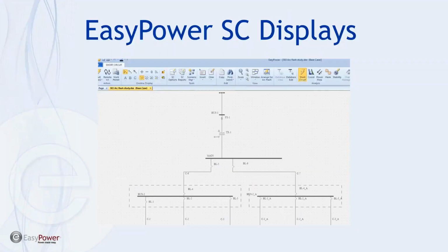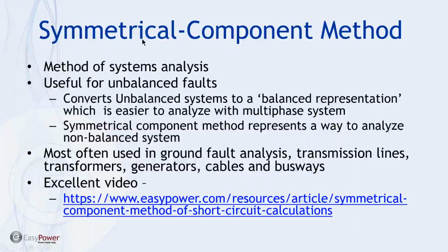Now, the next type of application of these terms is what's referred to as the symmetrical component method, and this is a method of systems analysis that's extremely useful for unbalanced faults. And basically it's a conversion of the unbalanced system into a balanced representation, which is easier to analyze, especially with multi-phase systems. And even though it's a technique that was developed 100 years ago, it's still useful today, especially in the age of computers where we have more analytical capability. It gives us a very convenient way to analyze unbalanced or non-balanced systems. It's most often applicable in ground fault analysis, transmission line applications, and transformers.